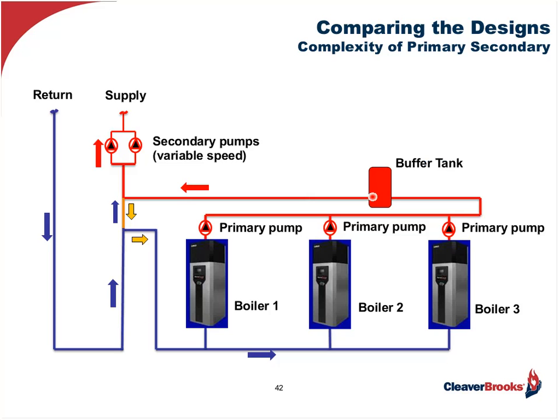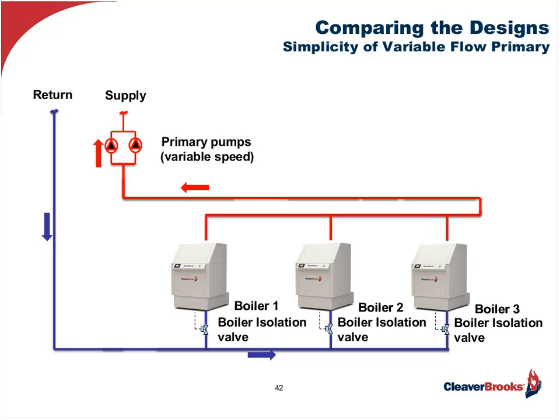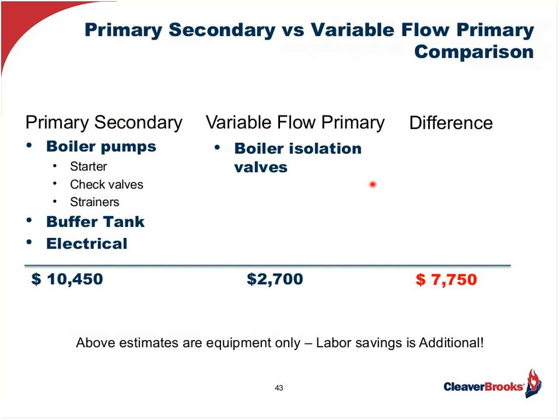In addition, most manufacturers will recommend you have some sort of buffer tank. And you have the decoupler, and especially if you're buying a hydraulic decoupler from a manufacturer, that's a cost there. Variable flow primary, by contrast, all you have is the boiler and the isolation valves. Simpler piping, no pump, no power. So in this example, we would have about a $7,700 installation savings. And that's just for materials alone. Generally, you can save a little bit on the installation as well.